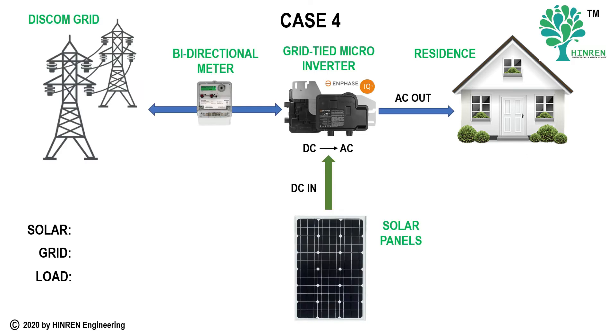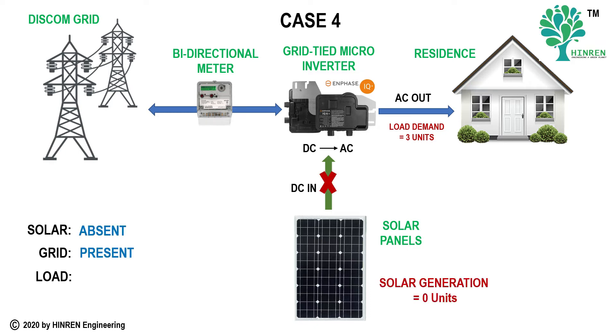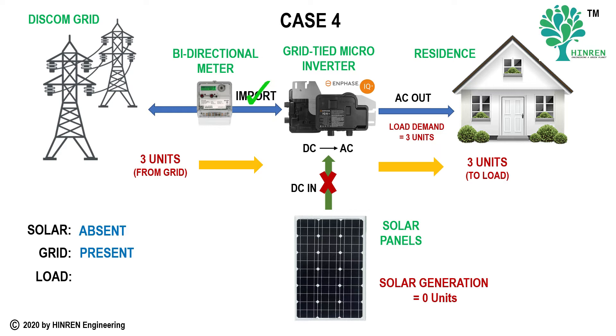In Case 4, there is a demand of about 3 units and the grid is available, however there is no solar — that is, it is night time. In this scenario, the entire load demand of 3 units is catered exclusively by the power utility or DISCOM grid. So obviously, there is only import of energy and no export. The amount you can draw is up to your sanctioned capacity, which is the sanction load fixed by the DISCOM.